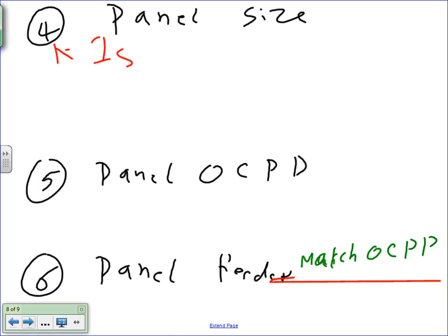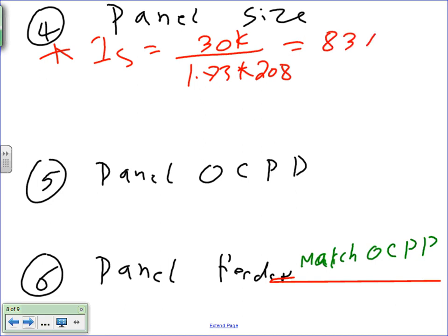The first thing you need to do is find the I secondary: 30K divided by 1.73 times 208 this time. Now because we moved to the secondary side, that will give me 83 amps. Step number 2 is to take the 83 amps and multiply by 1.25 because I will accommodate for continuous load in this panel, and that will give me 104 amps.